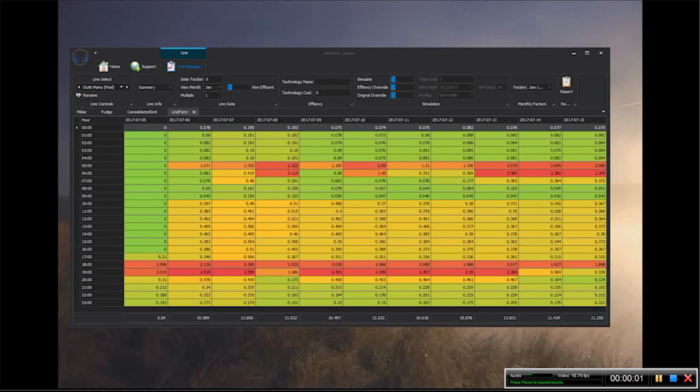In some cases, it's not possible to split the loads when we measure them. For instance, the outbuilding mains here has got a pool pump, a freezer, as well as an electric geyser that is on a timer. We can see in each one of those, we can see the freezer at night running. The geyser timer is on from 5 to 7 in the mornings, as well as from 6 to 8 in the evenings. You can see the geyser timer over there.